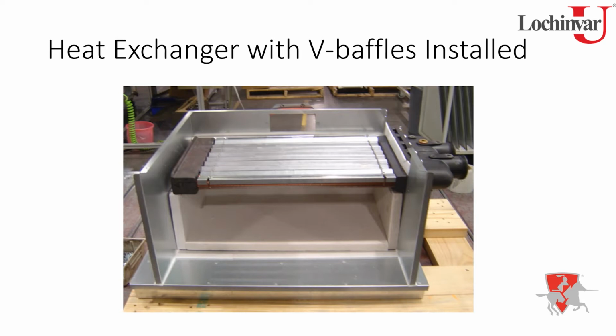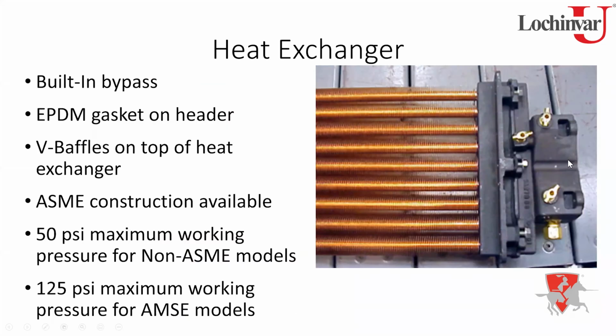The heat exchanger that we do see in this particular picture is a non-ASME. The heat exchangers are available for either ASME construction or non-ASME construction. The difference is going to be the heads. The non-ASME will be a polymer header, whereas the ASME standard will be a glass-lined cast iron header.